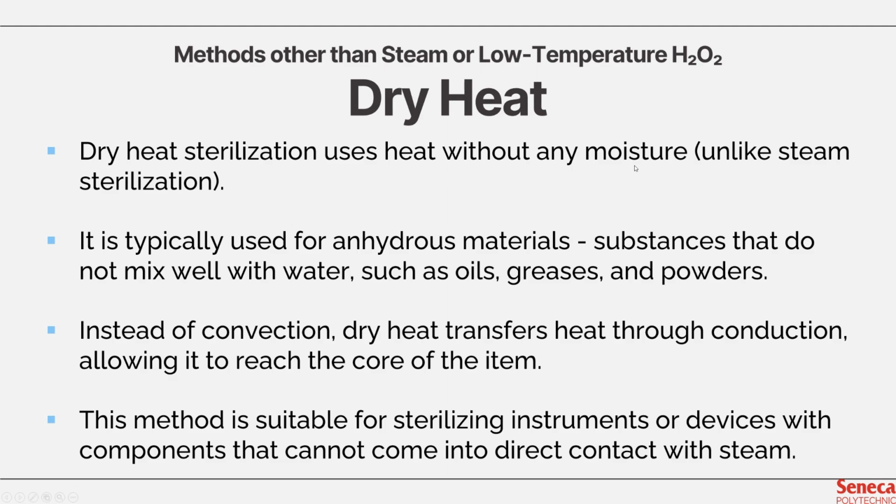So another method used for sterilization is dry heat. It operates without moisture and uses high temperatures to sterilize instruments. Unlike steam sterilization, which uses moist heat and convection, dry heat uses conduction. So that means heat travels molecule by molecule to reach the item's core. This is effective for materials that can't tolerate moisture, such as powders, oils, greases, and certain metal instruments.